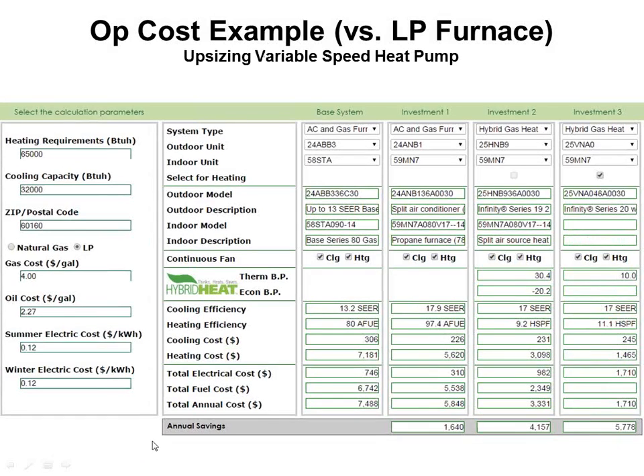I could also upsize the heat pump a little bit. So if you notice, I have this little box over here on this software tool. I know this is a really basic tool we're working with, but it's really quick and easy to give examples with. I have this little check box I can check. And now instead of giving me a 3-ton heat pump, it actually gave me a 4-ton heat pump. It upsized me one. It doesn't let me check that box on the 2-stage heat pump because it knows that upsizing a 2-stage heat pump is a bad idea and it'll kill you in the summertime for dehumidification. But doing it on a variable speed and going up a half or a whole size is okay.